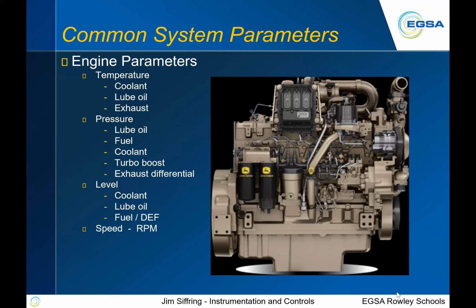Speed, as in RPM. RPM determines the frequency output of the genset, so we want to keep very close track of that. Vibration, knock, other mechanical type issues. We want to have sensing, say if there's water in a fuel system or something like that, we can sense that. Probably first and foremost these days is emissions. We want to keep track of our emissions. We want to keep track of NOx, O2, CO, all those sorts of things.